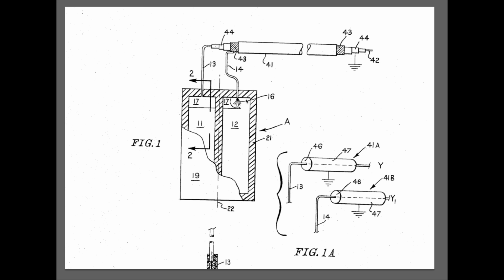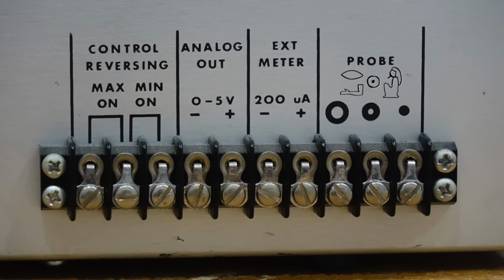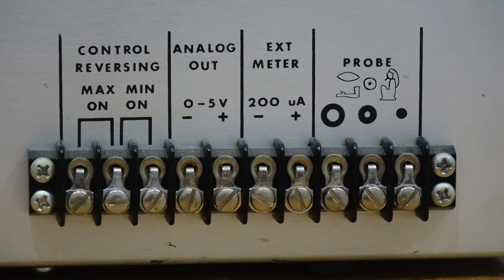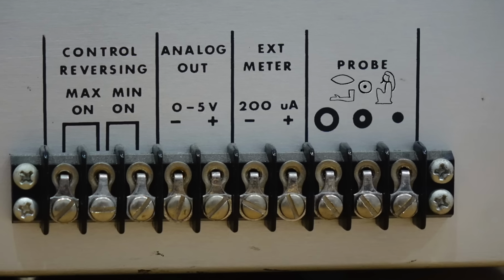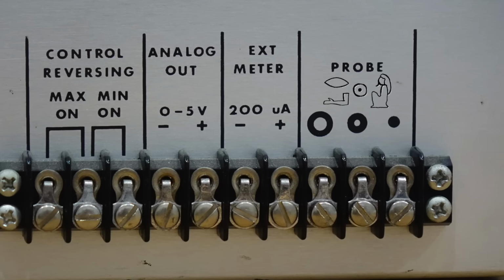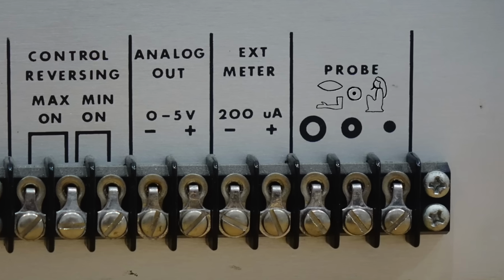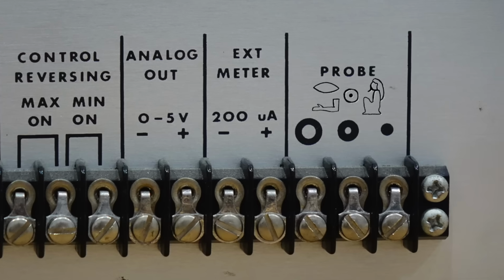And note that the probe is connected by what looks like a coax, but it's not a coax, it's a triax with 3 conductors in it. So it has a center conductor, which is connected to one side of the probe. It has a middle shield, which is grounded, and an outer shield that's connected to the other side of the probe. So our hieroglyphics make perfect sense now. It's a depiction of the 3 conductors in a triax cable cross-section. I bet you didn't know that Egyptians had invented triax. You learn stuff every day on this channel.